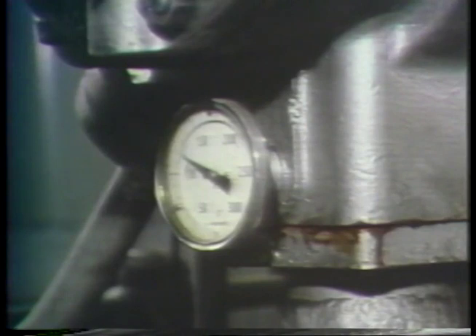Bimetallic thermometers use the fact that different kinds of metals expand and contract at different rates with changes in temperature. Two strips of different kinds of metal are joined together. When temperature increases, one strip expands more than the other, causing the bimetallic strip to bend. If temperature decreases, the strip bends in the opposite direction. The amount that the strip bends depends on the amount of temperature change.